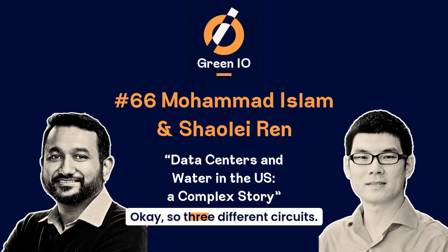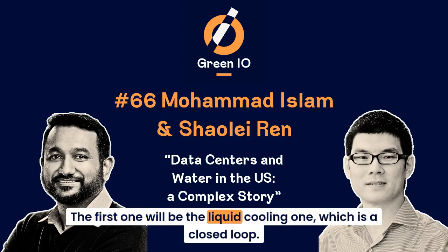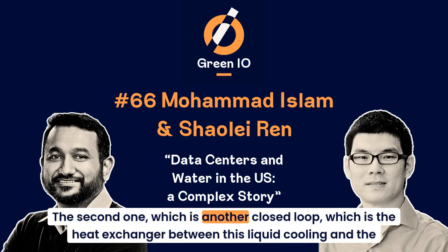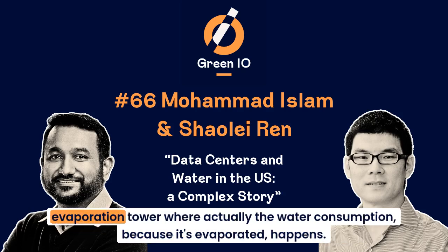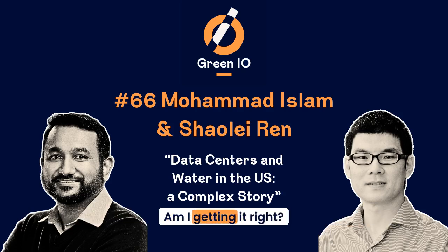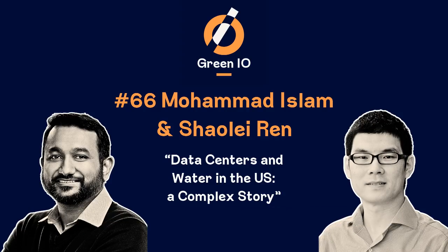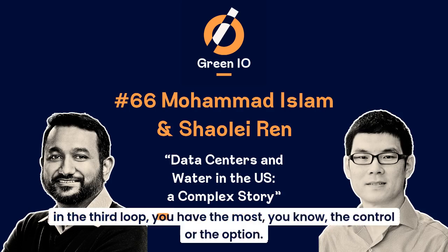So three different circuits: the first is the liquid cooling loop, which is closed. The second is another closed loop, the heat exchanger between this liquid cooling and the evaporation tower, where the water consumption happens because it's evaporated. Am I getting it right? Yes. And in the third loop, you have the most control or the option.